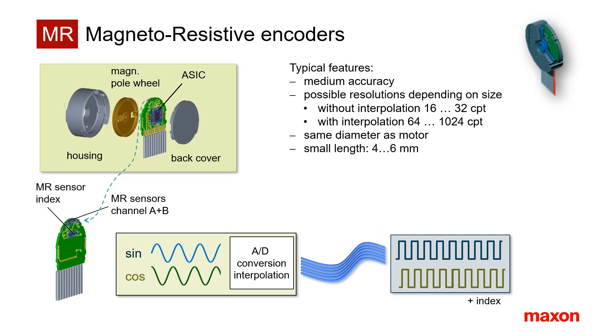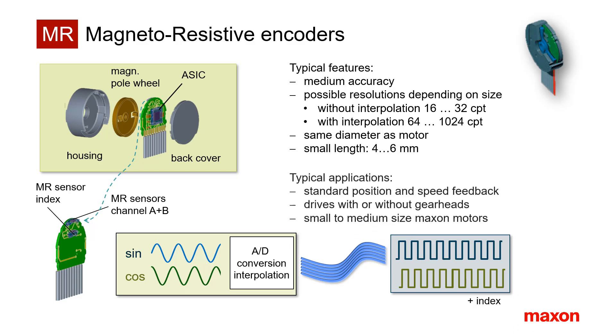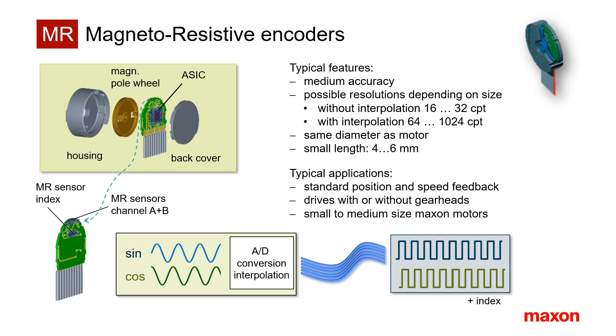The angle deviation from the true mechanical position can be as high as several degrees depending on diameter — about 5 to 10 times less accurate than optical encoders. However, it is still the perfect encoder for many standard applications that don't require excessive precision, particularly in combination with gear heads or other drive mechanics that exhibit backlash and elastic behavior.